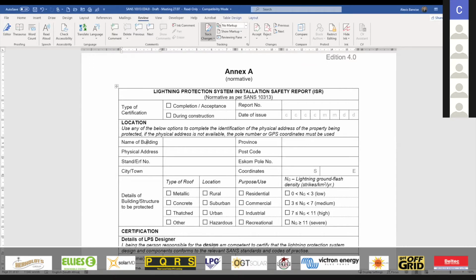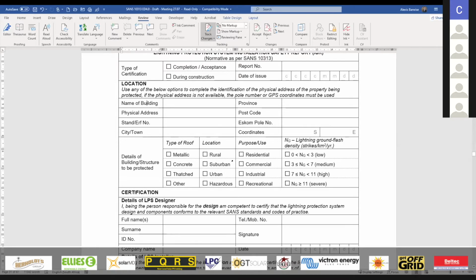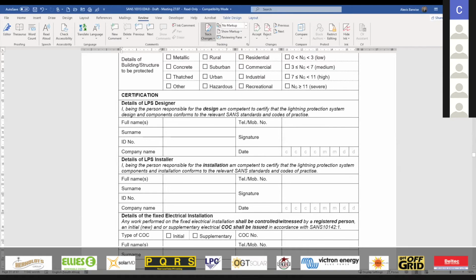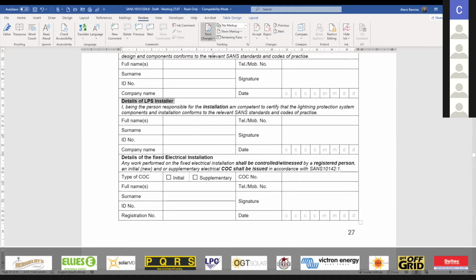So here you would have a lightning ground flash density value, what the purpose of use was, what type of roof is being used, and it would be signed off by the designer, by the installer of the lightning protection system, and finally, to close the loop, by the actual registered person. So the installation electrician would then also co-sign the COC number, and that closes the gap.